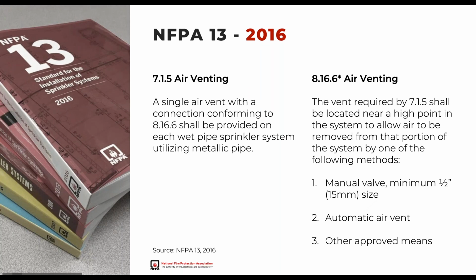So in 2016, they introduced language that said, and I hate reading slides here, but the language says, a single air vent with a connection conforming to 8.16.6 shall be provided on each wet pipe sprinkler system utilizing metallic pipe. What that means is all wet systems that have steel pipe in them have to have an air vent on them. Each and every wet pipe system, and it says shall, not should, it's shall, which means you have to do it. And that single air vent per system shall be located near a high point of the building, and it can be constructed as either the simplicity of just a half-inch valve, or it can be an automatic air vent or other means.